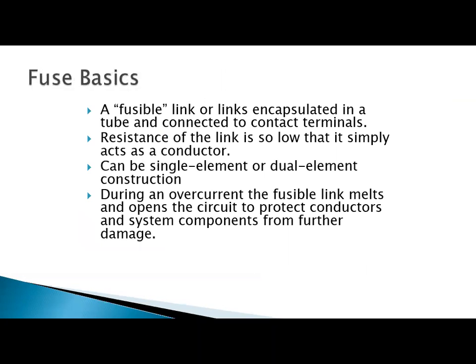When I first started in the trade, fuses were very prevalent. And one thing about a fuse is this: we can tamper with them. When we first started with fuses, here's what we would discover: if we put a 15 amp fuse in and we had too many appliances or pieces of equipment on that fuse, the fuse would open up and we would be without power. So they would take the 15 amp out and put a 20 amp fuse in, and that would compromise the integrity of our conductors, and it could damage equipment also.